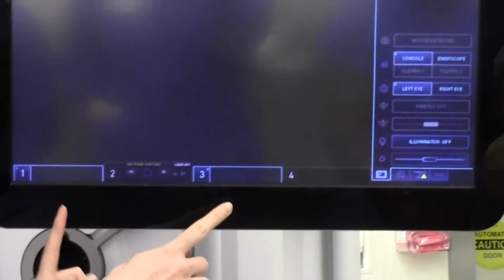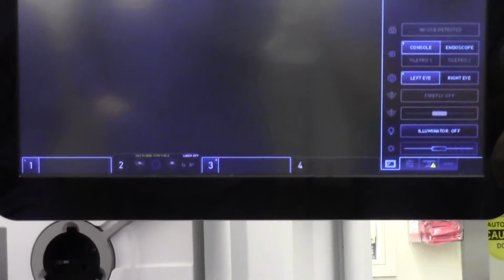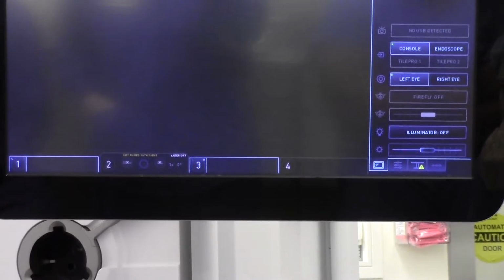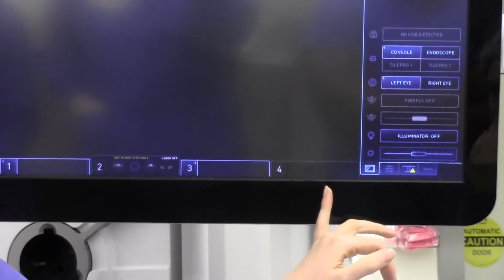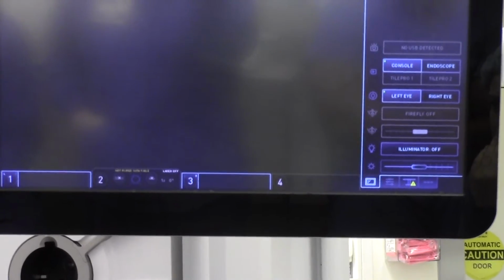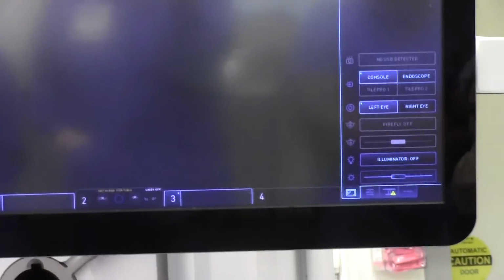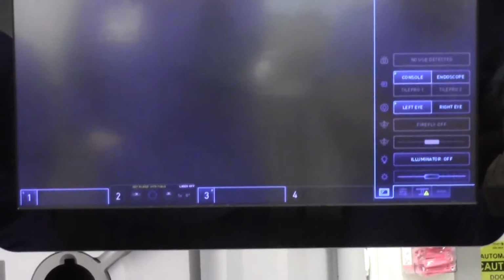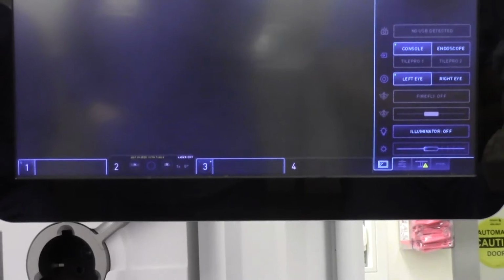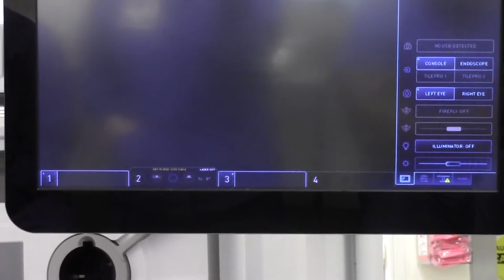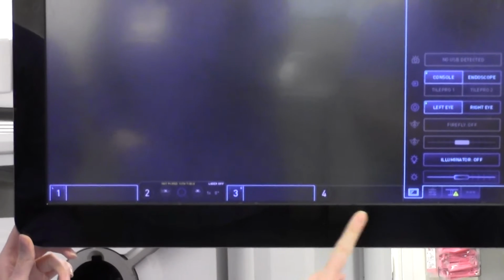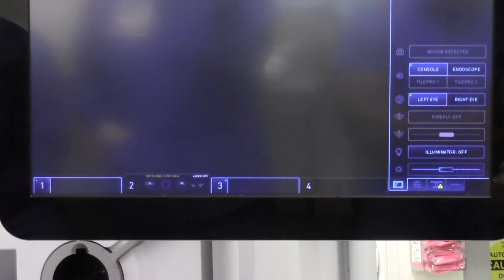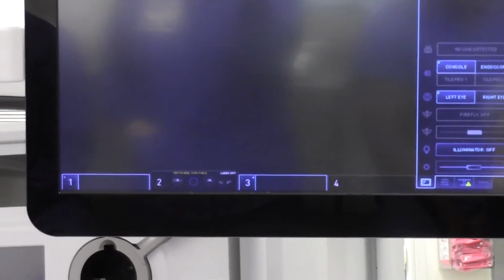So I like to point this out. It's highlighted on these 2 because those are the active instruments that the surgeon would be controlling if you were docked. Sometimes, like you were kicking that arm swap pedal earlier, the surgeon will accidentally switch over to the other arm and they'll sit there and go, my instrument's not working. Arm 3, my instrument in arm 3 is not working. And it's grayed out. That means they've accidentally kicked over. Just tell them to kick the arm swap pedal and they'll switch back. Oh, and that's how you kept knowing I need to kick it again. Yep, okay, because I could see on the bottom of the screen you kept jumping back over. So you're only ever going to have 2 highlighted. Yep. It's one of those things that people don't think happens frequently in cases, and it happens all the time. So, yeah.